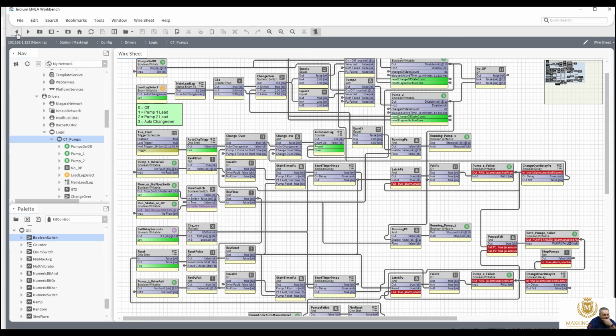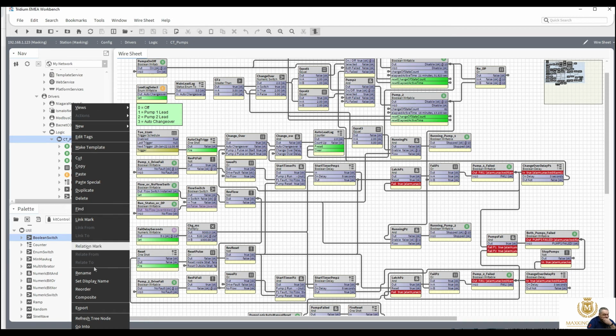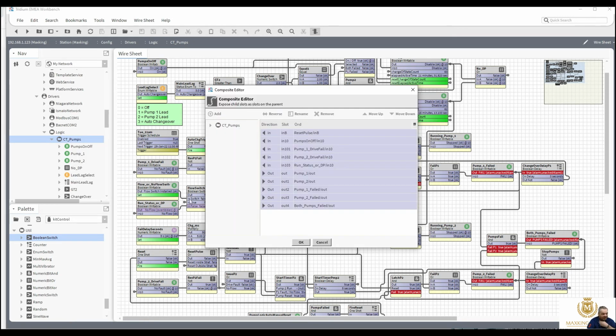What I think I might just do as well is take out pump 1 and pump 2 running times, so we can see it from there rather than that coming into the logic. So pump 1, discrete totalizer, elapsed time. Now that's going to give me a numeric. No, we won't use that one, because that's going to give a value that we won't understand.